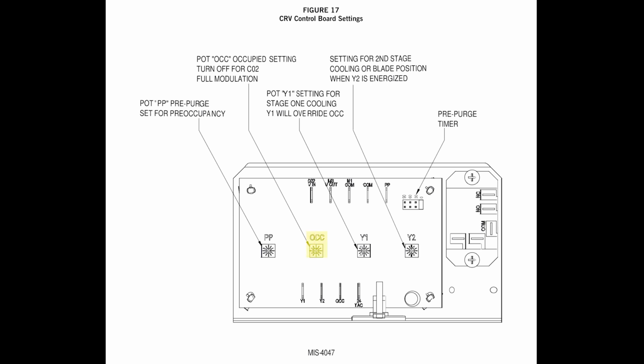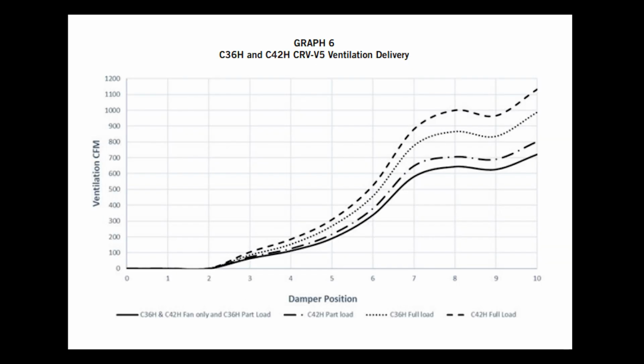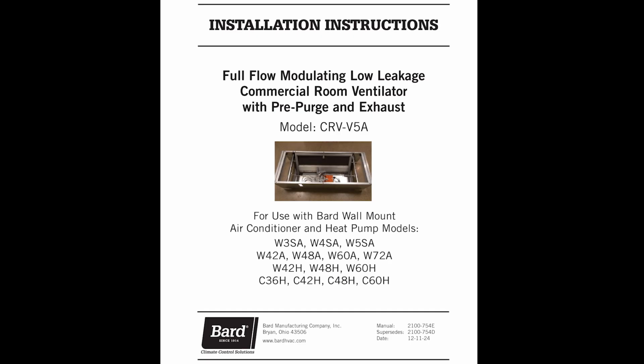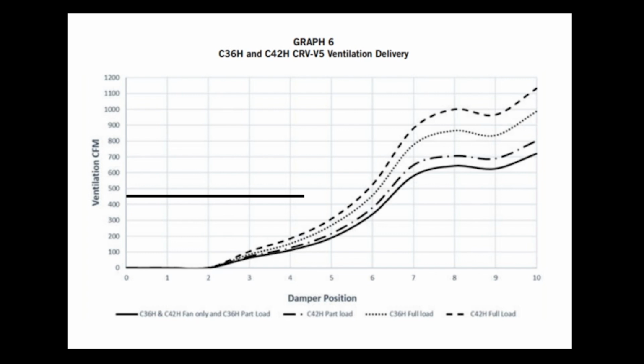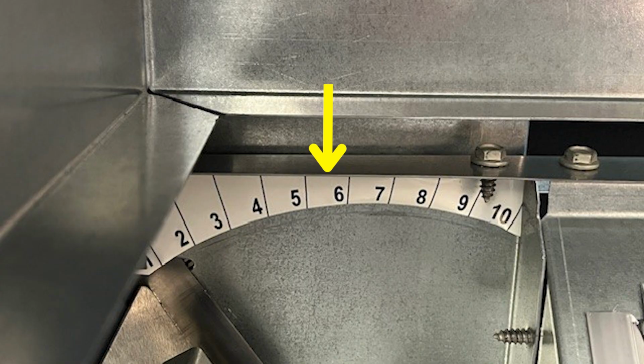Set the OCC pot first. Use the CFM graph charts for this unit's vent device found in the install manual 2100-754 on pages 19 through 21 and locate your specific unit model number. For 30 students, 450 CFM and this unit, adjust the OCC pot to move the damper to position 6 on the decal inside the unit behind the filter. The damper travel time to position 6 is about 65 seconds.